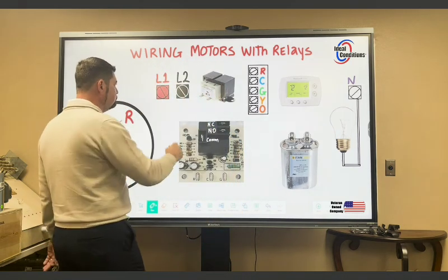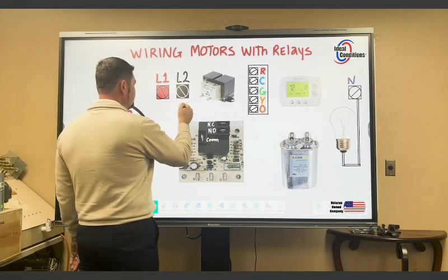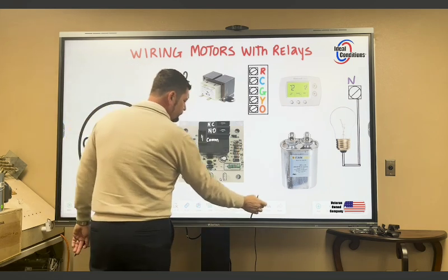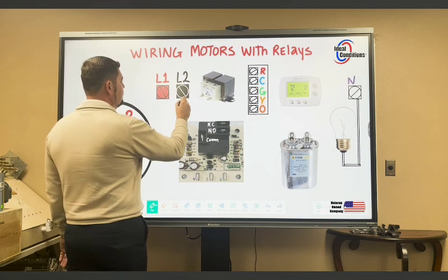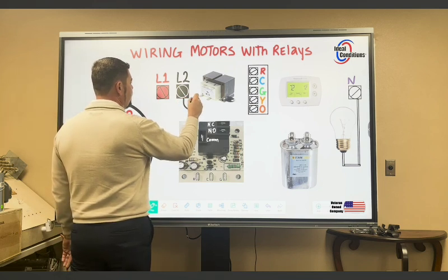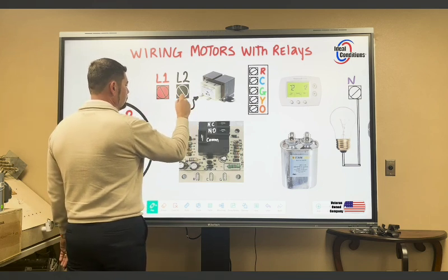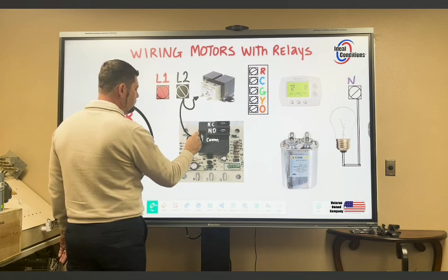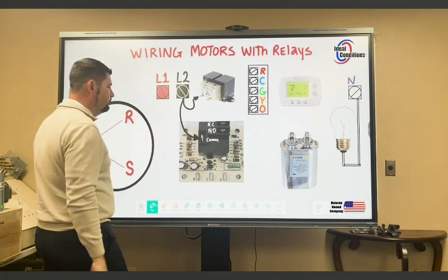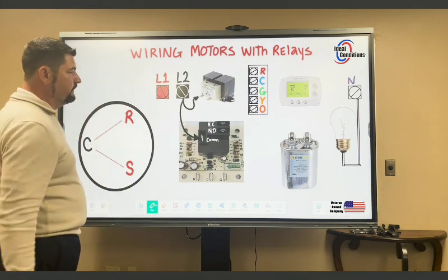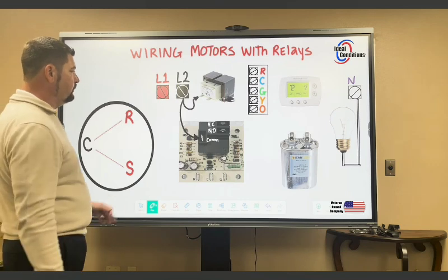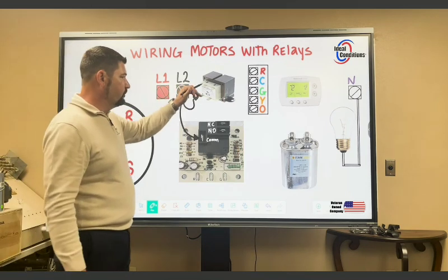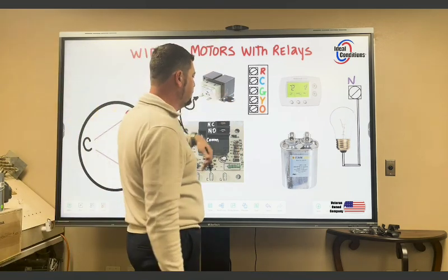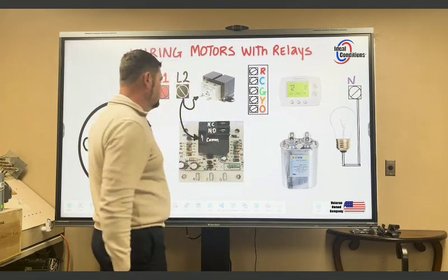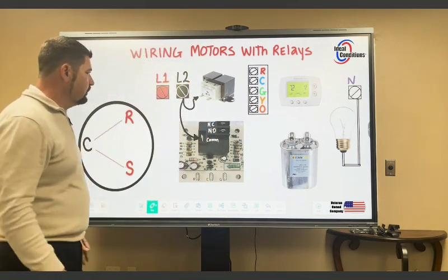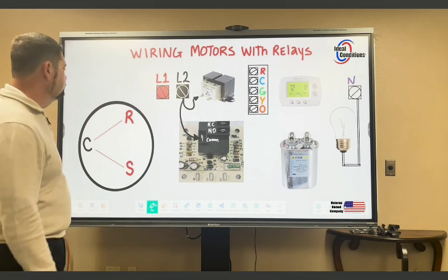Okay. We're going to go ahead and take L2. We're going to go ahead and land power on the transformer. We're going to go ahead and land power on common. This is also good if you had to replace everything in your control panel with a new motor, new transformer, rewire your terminal block, new capacitor, new thermostat, new blower control board. If you had to rewire everything, this is what you would do.